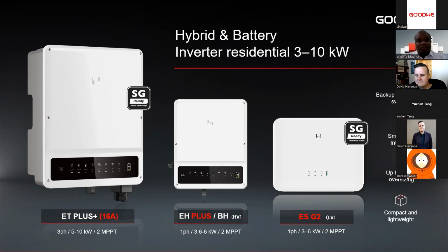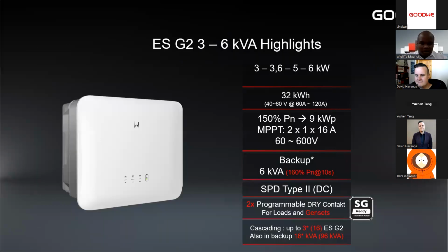Some of the unique features of our hybrid or energy storage inverters are that they have a UPS level switching time of less than 10 ms. You can do smart home integration, and they support DC oversizing of up to 150%. They are really compact and lightweight. So, for example, we have our ESG2 series. This is our hybrid inverter for single phase. It also supports low voltage batteries and comes in sizes of 3, 3.6, and 6 kilowatt. They can support a battery bank of up to 32 kilowatt hour.